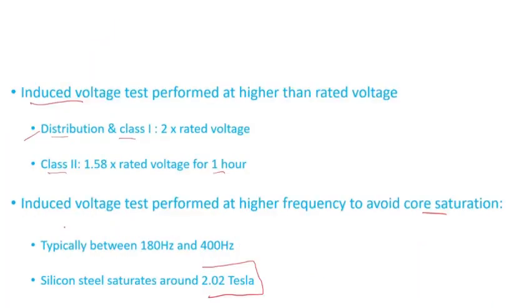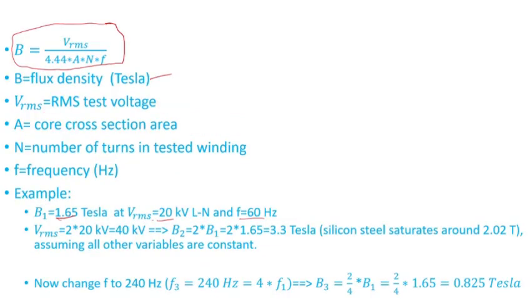...and Class I, you apply two times the rated voltage. So if you increase the voltage to twice the rated voltage, two times 20 kV is 40 kV. The new flux density B₂ is two times B₁, because the only thing I changed is V_RMS. So I multiply by two, and obviously this here is B₁.